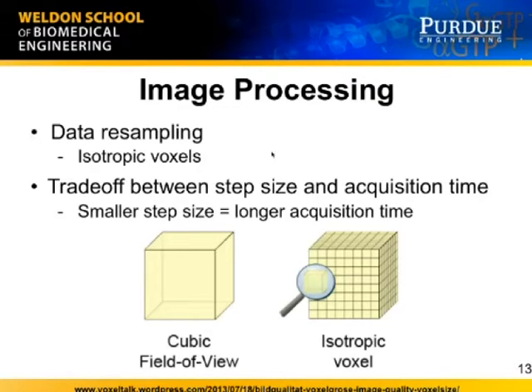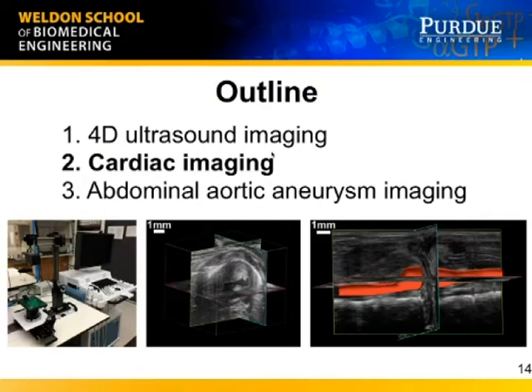As mentioned previously, there is a trade-off between the step size and acquisition time. The smaller the step size, the longer the acquisition time, simply because you need to collect more serial images to acquire data from a specific length with smaller step size. However, with smaller step sizes, less extrapolation is needed to merge the images between adjacent slices. So if you want to get the image quality that you want and you want to acquire the image within a specific period of time, you might want to consider what would be your best optimal step size. Now that we have established the procedure used to acquire the 4D data sets, we will continue by discussing how this 4D ultrasound imaging technique can be used in cardiac imaging.